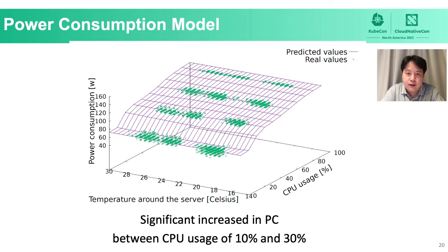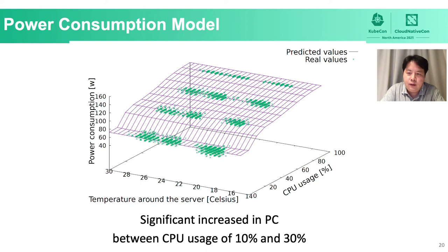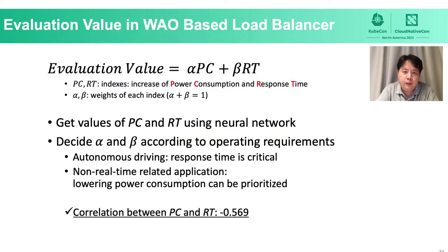This 3D figure shows the result of the server power consumption model in this experiment. The horizontal axes indicate temperature around the server and CPU usage, and the vertical axis indicates power consumption. Blue lines are predicted values from the power consumption model, and the scattered points are real values from the test data. The most remarkable finding is that the server's power consumption increased significantly when the CPU usage was between 10% and 30%. In addition to the power prediction model, we also create a response time model to evaluate the response time of applications.